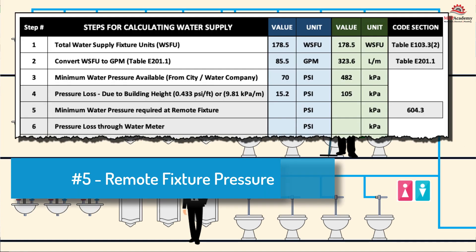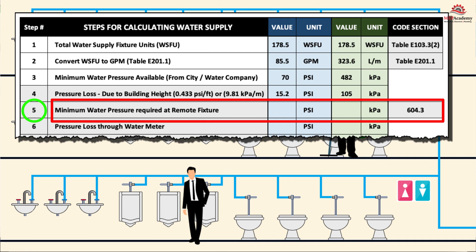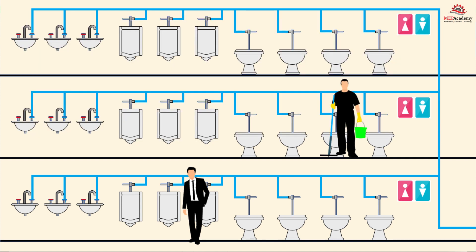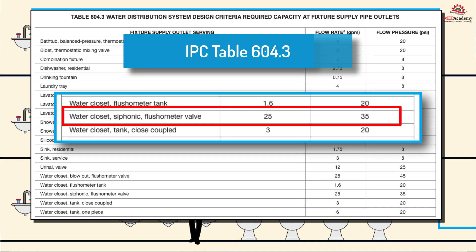Step 5: Minimum Pressure Required at Remote Fixture. This ensures the fixture has enough pressure to operate properly. Each fixture requires a different amount of pressure, so it's important to select the remote fixture with the greatest pressure requirement. Using IPC Table 604.3, the siphonic water closet with a flushometer valve requires 35 PSI or 241 kPa for proper operation.